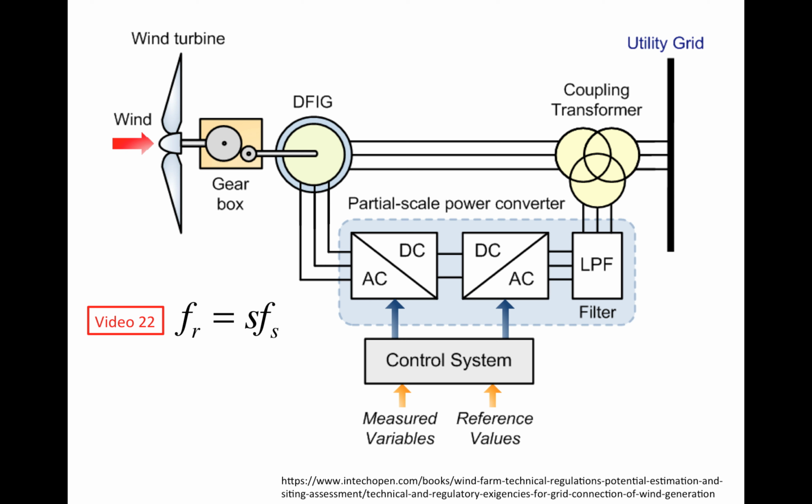The excess mechanical power delivered to the generator's rotor, which is sometimes known as the slip power, is pretty much just dissipated as heat on the resistor and serves no useful purpose. So the Optislip system allows for very high slip operation.